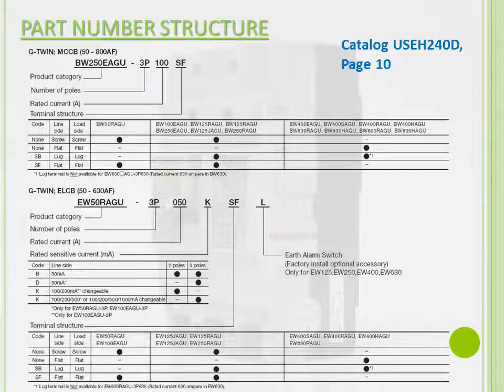Now let's look at the part number structure for the G-Twin breakers. You can find this at Catalog USEH240D on page 10. The part number structure for the MCCB comprises the product category, the number of poles, rated current, and terminal structure. For the ELCB, there's another category, the rated sensitive current.